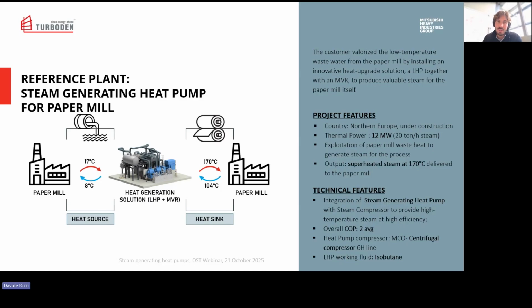We have a heat pump that takes from 8 degrees C to produce 1.5 bar absolute steam, and that steam is then sent to a two-stage steam compressor that produces the output required by the process. The working fluid for the heat pump is natural - indeed, we use isobutane. The overall COP is 2 as an average.